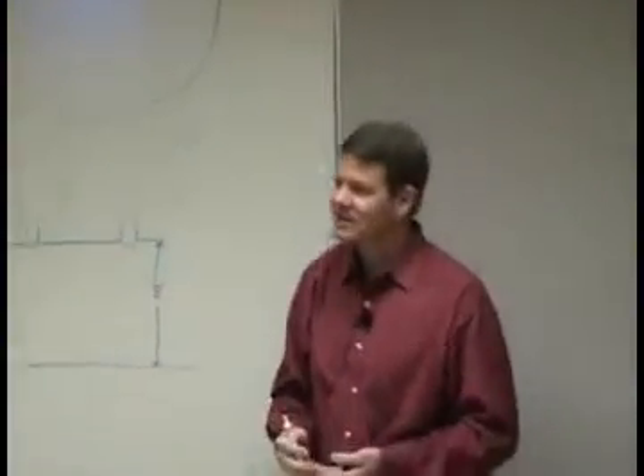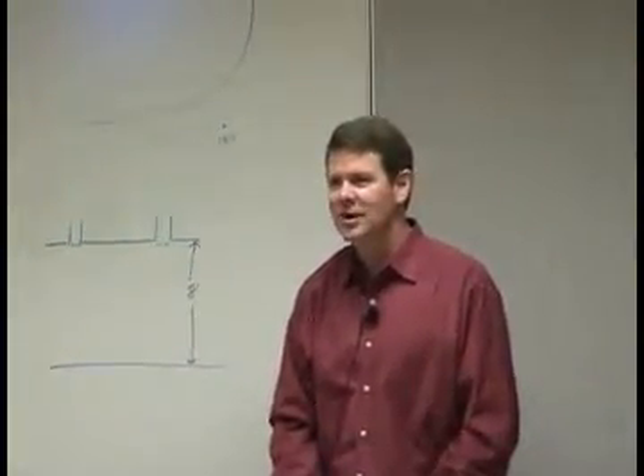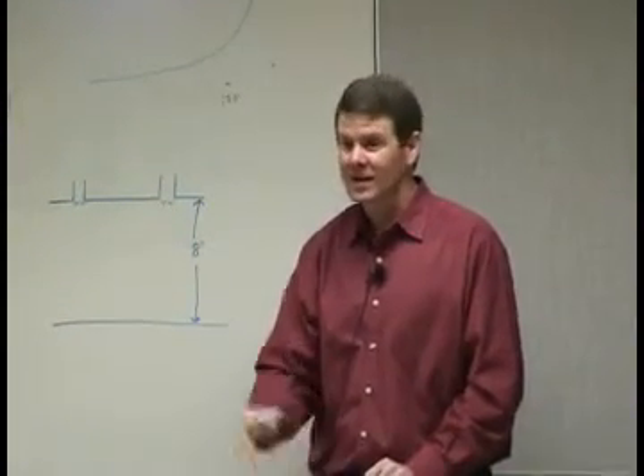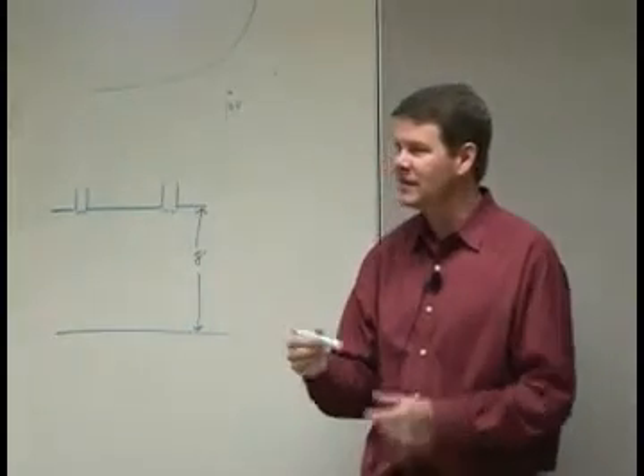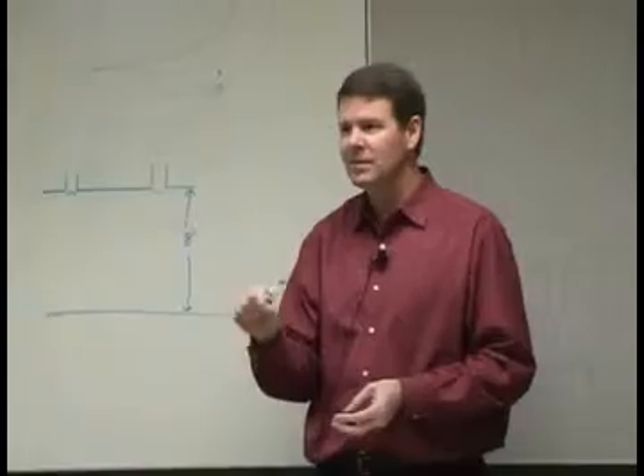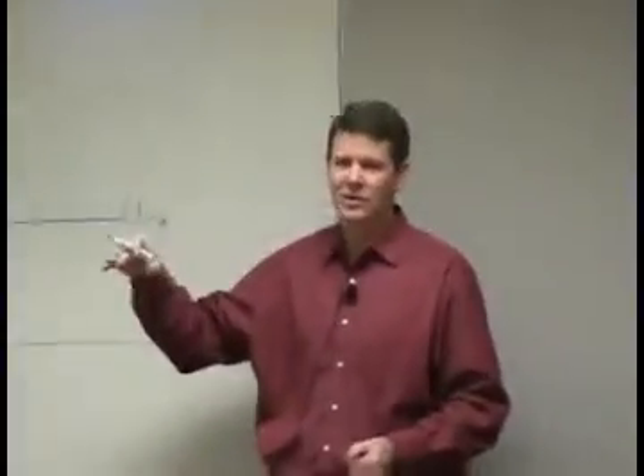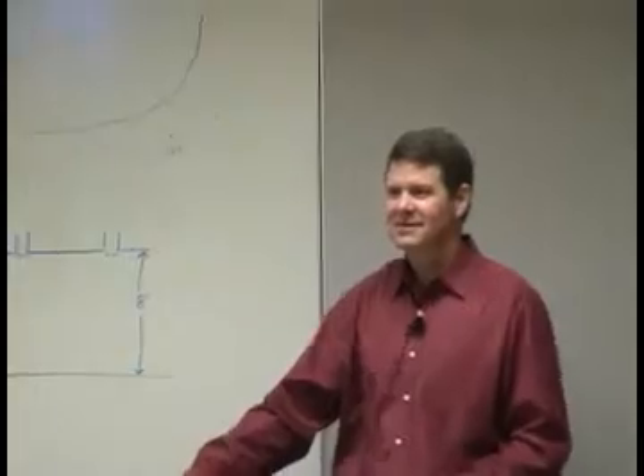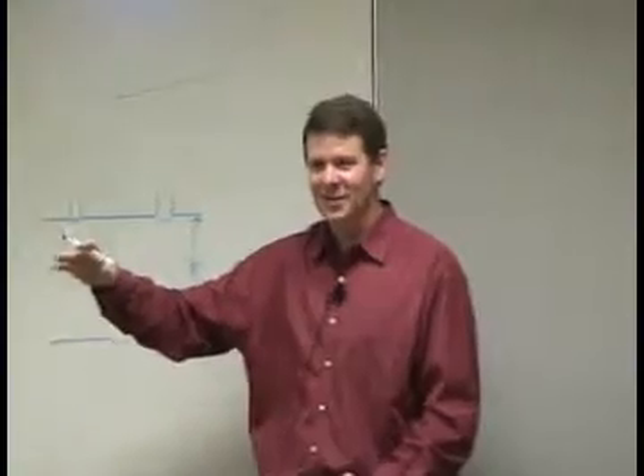So has anybody sat there and watched your Continuum screen at the VAV box reading? Look at the input, not the numeric. We'll have a CFM numeric, but don't look at that, look at the actual input. And what happens is the CFM will go down, you'll see 500, you'll see 400, you'll see 0. And the box says, oh crap, I gotta come back open again. And so the box will open up ever so slowly. And then, oh, we got 500, we got 400, we got 0. And it's going to sit there and do that all day, forever, because we cannot accurately read when we get down that low.